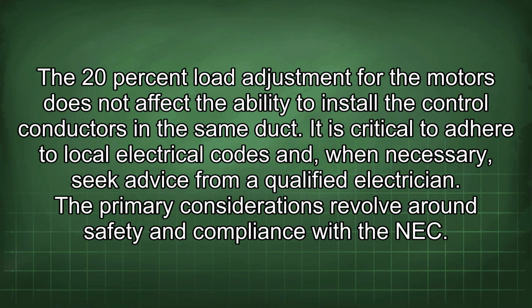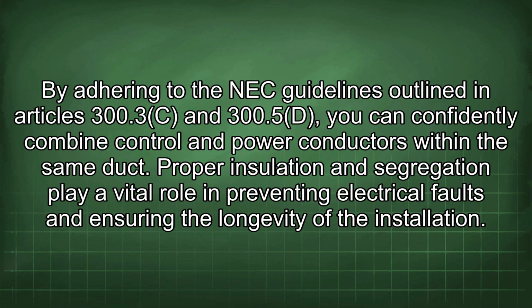The 20% load adjustment for the motors does not affect the ability to install the control conductors in the same duct. It is critical to adhere to local electrical codes and, when necessary, seek advice from a qualified electrician. The primary considerations revolve around safety and compliance with the NEC.